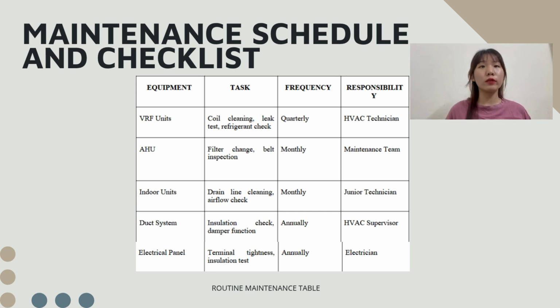Now let's look at the routine maintenance schedule and checklist, which ensures all essential systems operate efficiently and safely. Starting with VRF unit. This requires coil cleaning, leak test, and refrigerant checks on a quarterly basis. This task is carried out by the HVAC technicians. For the AHU, air handling unit, regular filter changes and belt inspections are performed monthly by the maintenance team.